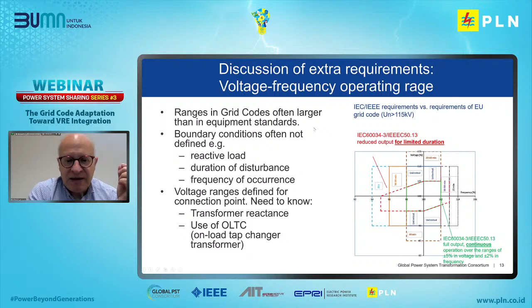Generators are required to be able to run in certain voltage and frequency ranges, but the grid codes impose these ranges at the point of connection. So the step-up transformer plays a very important role in the ability of the generating unit to fulfill the requirements imposed by the grid codes. Could you please go to the next slide?